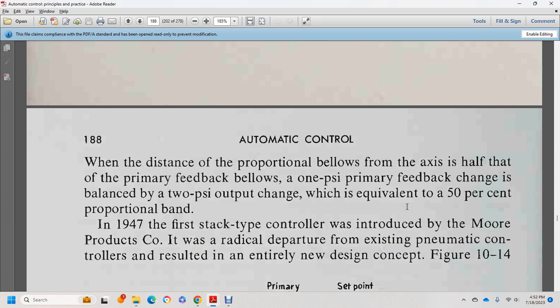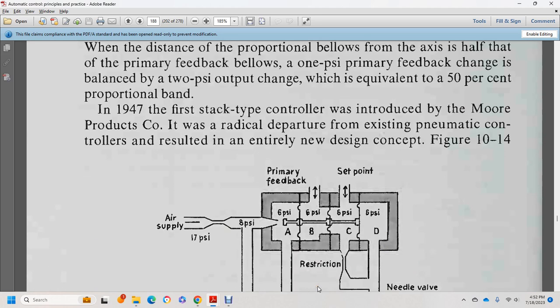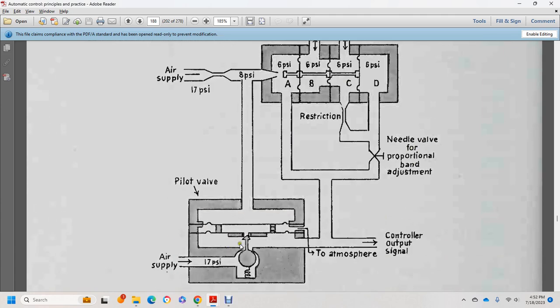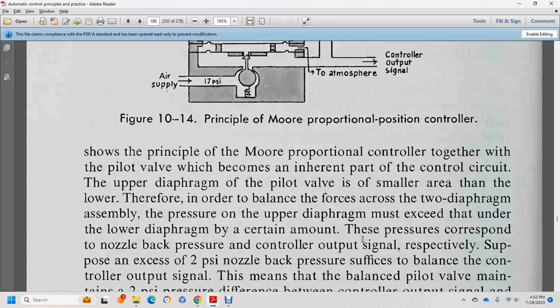In 1947, the first stack-type controller was introduced by the Moore Products Company, with a radically new design concept. Figure 10-14 shows the air supply, restriction, primary feedback, four-way valve, set point, primary feedback, needle valve for proportional adjustment, and pilot valve. The principle shows the pilot valve becoming an inherent part of the control circuit. The upper diaphragm has a smaller area than the lower, so to balance the forces across the two diaphragms, the pressure at the upper diaphragm must exceed that under the lower diaphragm by a certain amount.